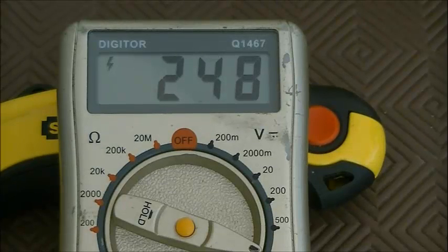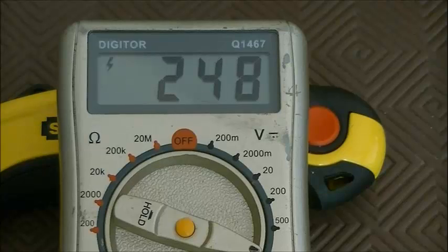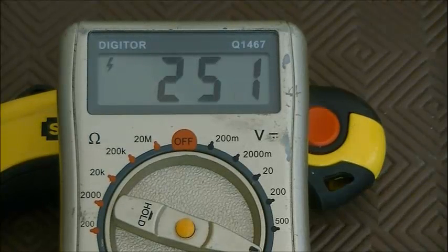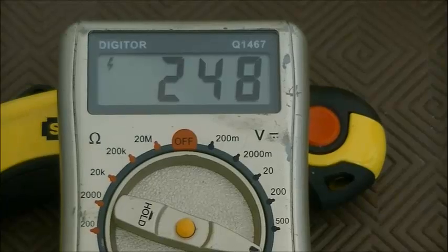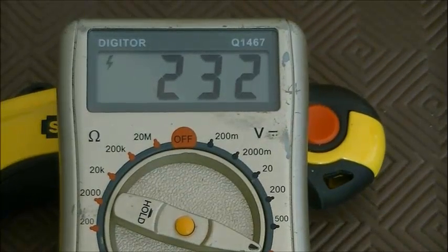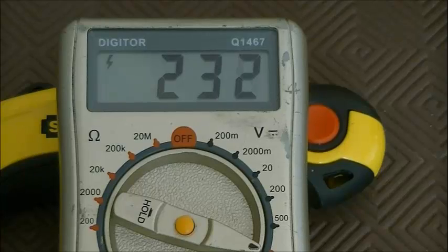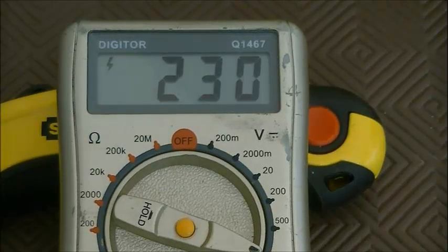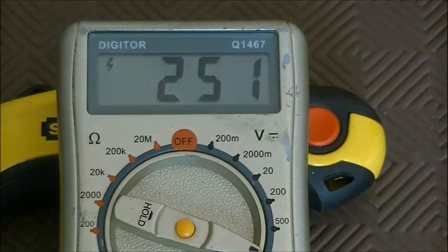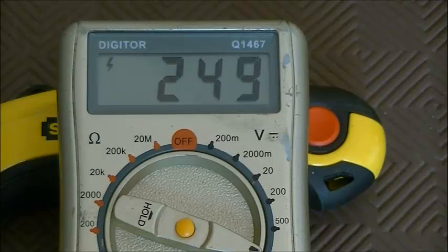With the magic of editing, I have now moved the voltmeter to the end of the lead, and you can see it reads mains voltage, which is what you would expect because there's no current going through it. And I will turn the jug on, and you will see the voltage drops to 230, which is 10 volts less than we were getting on the mains voltage with the jug on. So that means we're losing roughly, give or take a bit, 10 volts through the 25 metre extension lead. Remember, we expected to get 25.